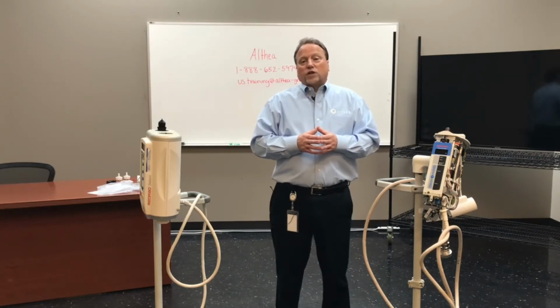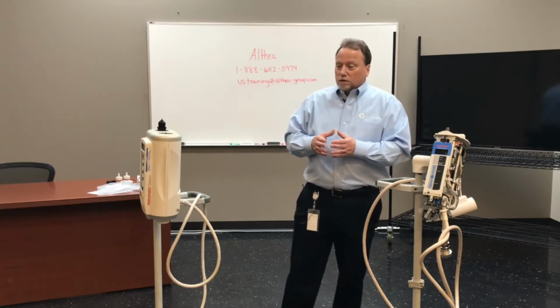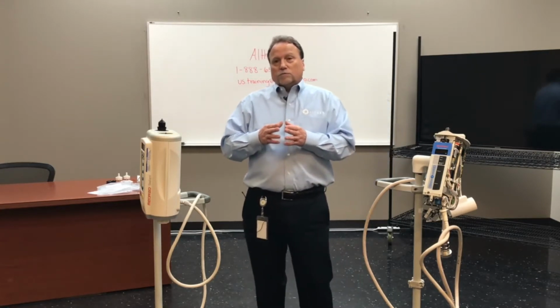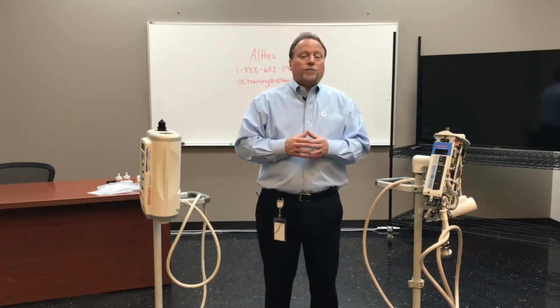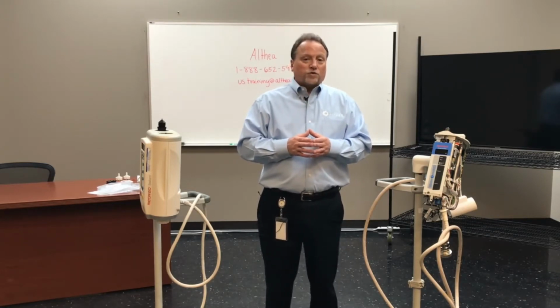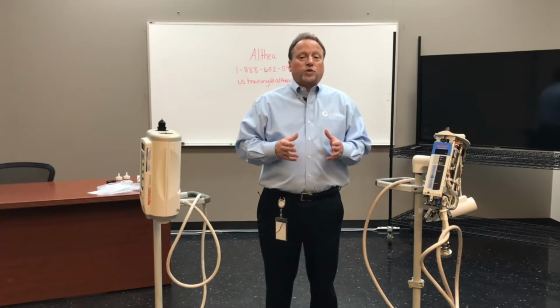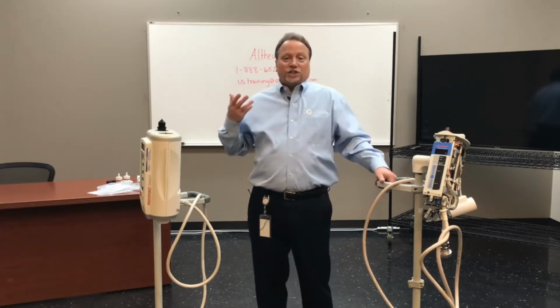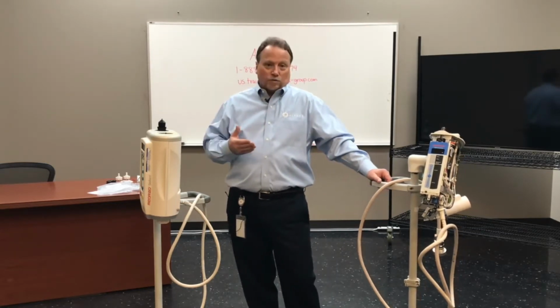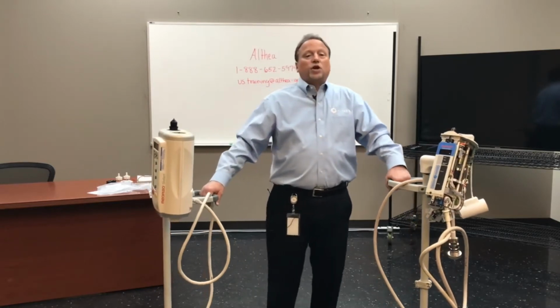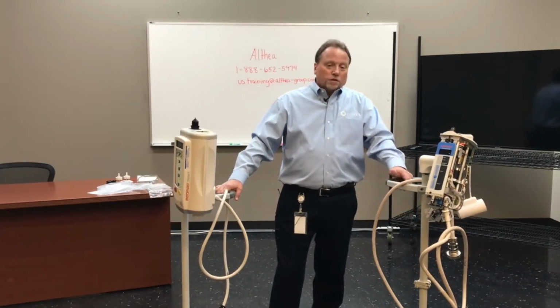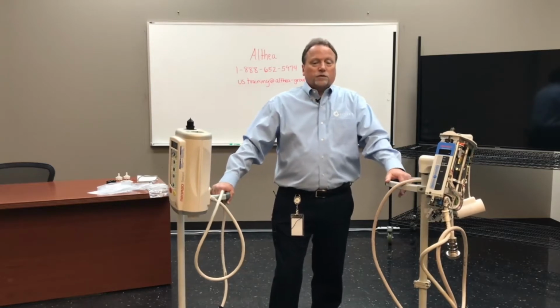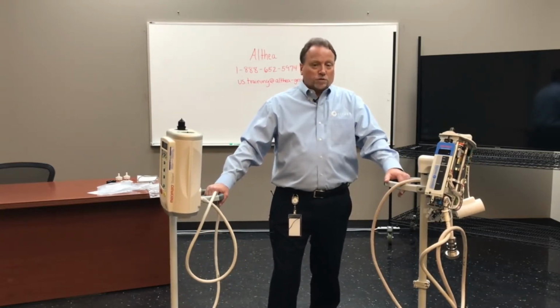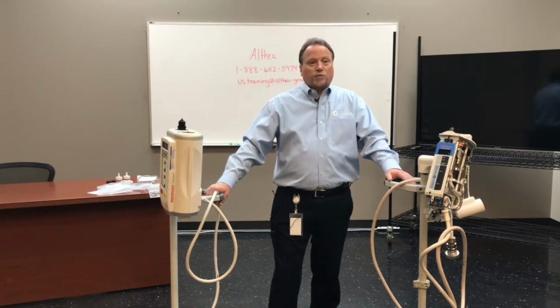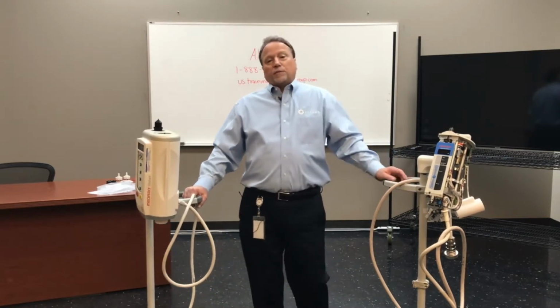Once contrast gets on the injector and on the gaskets, those gaskets need to be replaced. The gaskets harden from the contrast, and once hardened, they're no longer doing the job of keeping additional contrast out of the injector. Contrast is the number one issue causing problems with the injector—contrast intrusion, we see it all the time. Number one problem. So, PM kits.